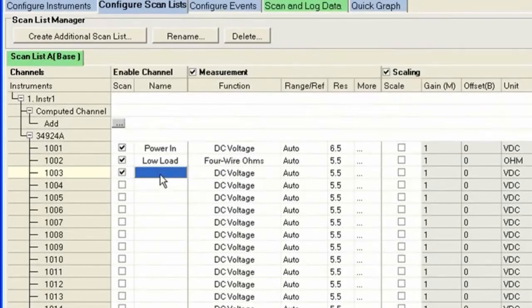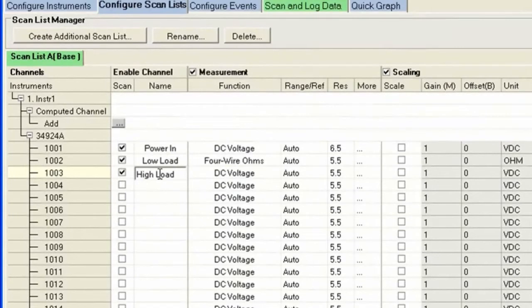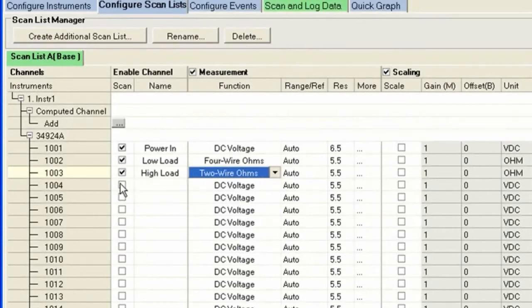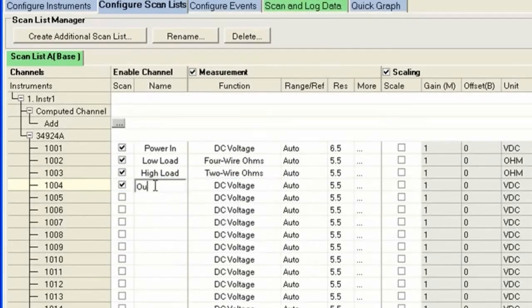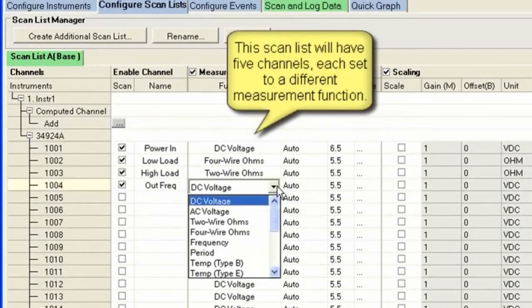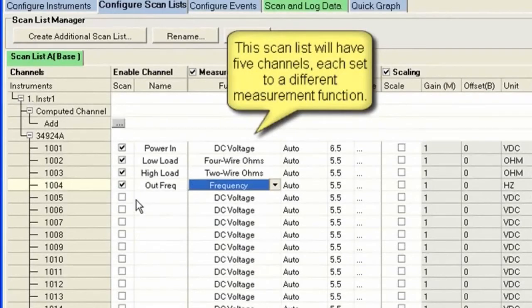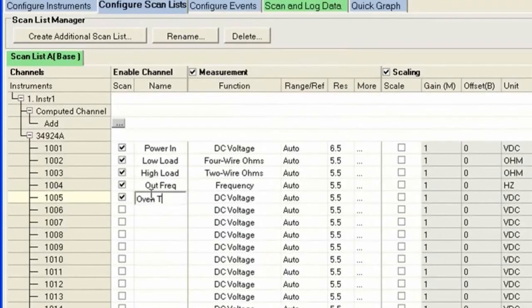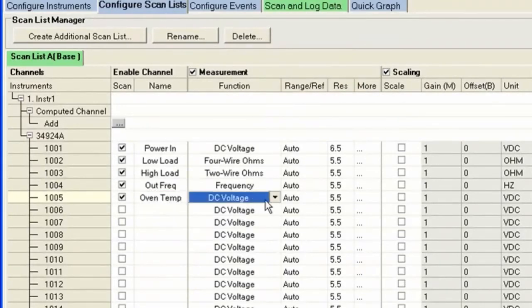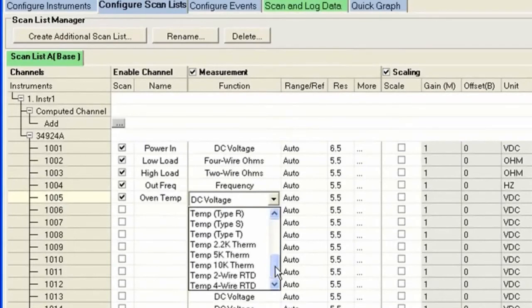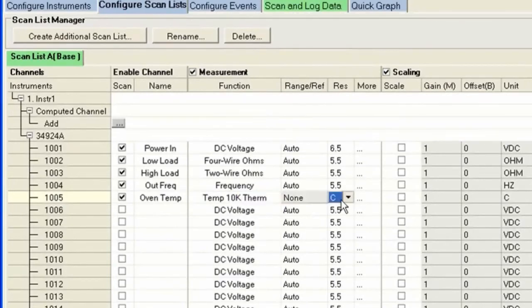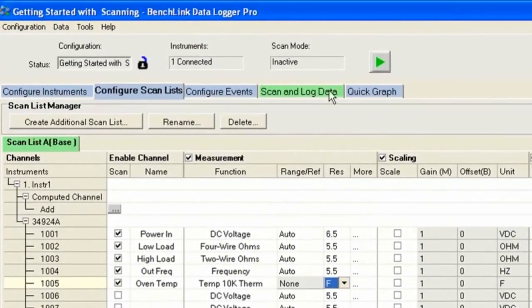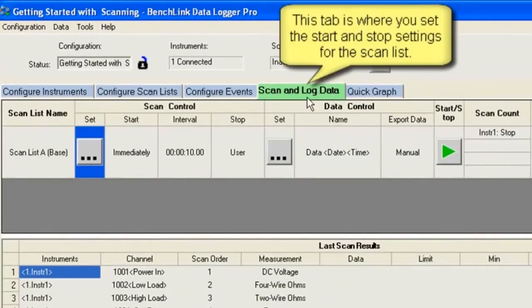The next channel, channel three, I'm going to look at a higher impedance load. So I'm not as concerned about the wiring, so I'm going to go ahead and use a two wire ohm technique on that to make the measurement. Next, I'm going to look at the output frequency. So I'm going to come down and find frequency in my pull down list. And then on the fifth one, I'm actually going to look at the oven temperature. Now we can use a bunch of different sensors. These are all universal inputs, so I can select almost any kind of temperature sensor. In this case, I have a 10K thermistor, and I'm going to measure it in degrees Fahrenheit. So that sets up my scans individually, what they're going to do on each channel.